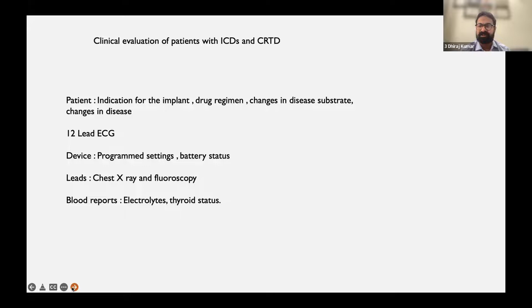You have to look at a 12-lead ECG because devices often provide you with 1-lead ECG data. 12-lead ECG is invaluable. You can look through the device and program settings, battery status, and the EGMs of the event. Looking at chest X-ray and fluoroscopy are very important because that will give you a hint about device malfunction. And finally, not only all this, but looking at blood electrolytes, because often enough hyperkalemia can lead to very tall T waves, which might sometimes be oversensed. Thyroid status is also important.